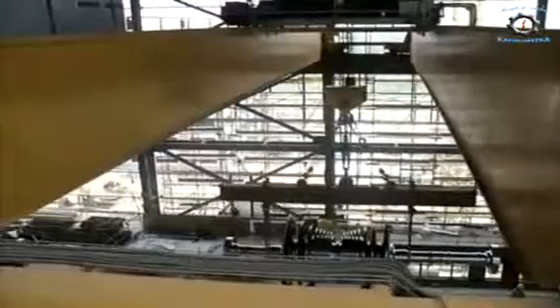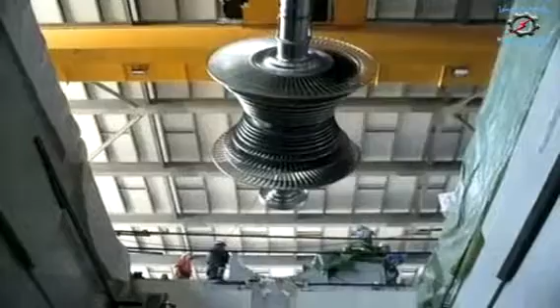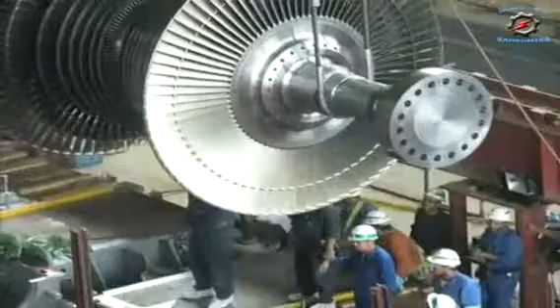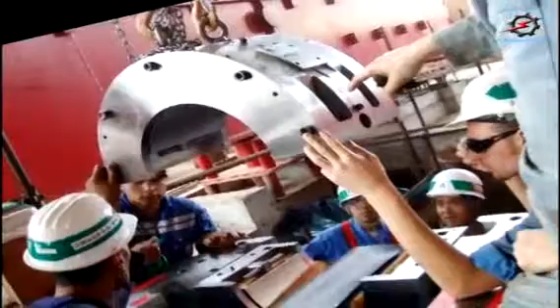Kahromika installed the high-pressure turbine rotor, which weighed 38 tons, and 2 rotors for low-pressure turbines, each one of them about 50 tons. The 3 rotors were aligned and coupled together with the highest quality and accuracy possible, reaching 24 meters long. The turbine and generator have 8 bearings.